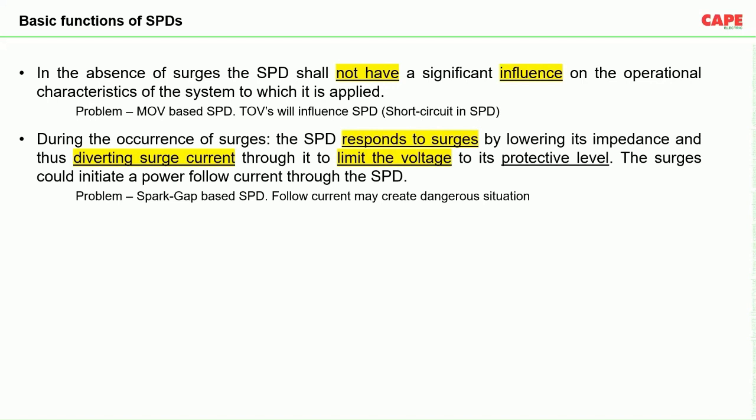The second basic function: during the occurrence of surges, the SPD shall respond by lowering its impedance and diverting the surge current through it to limit the voltage to its protective level. Once there is a surge, SPD immediately does two things: first, it creates equipotential by limiting the voltage to its voltage protection level; second, it diverts the surge current to earth or source, as applicable.